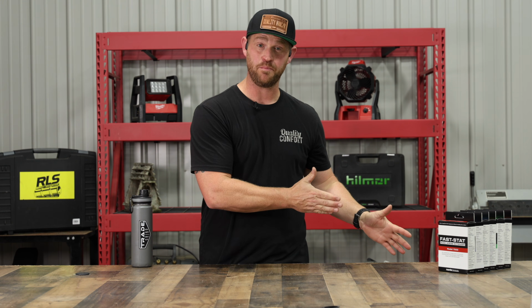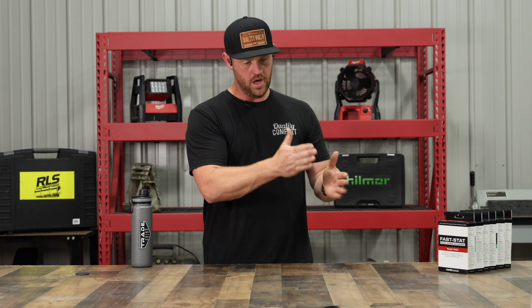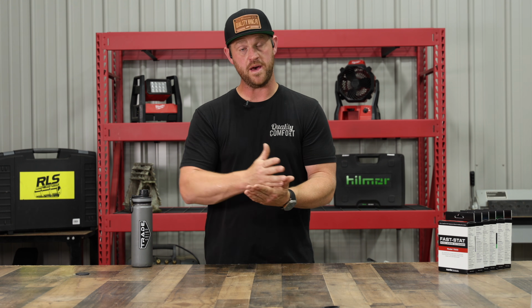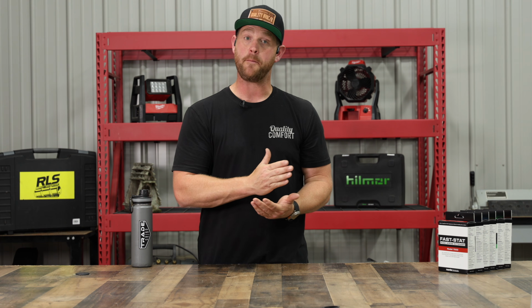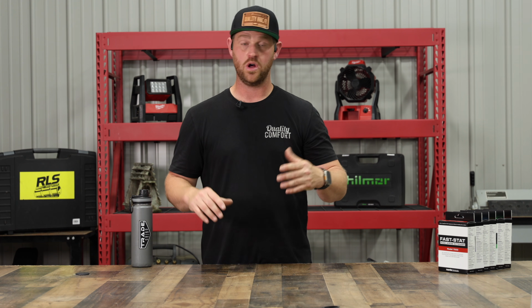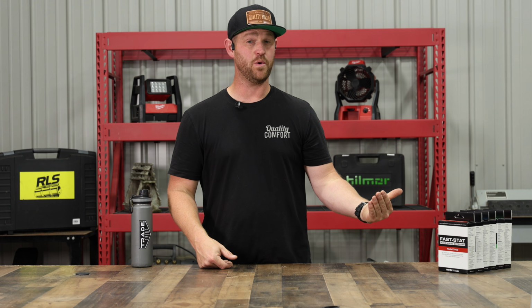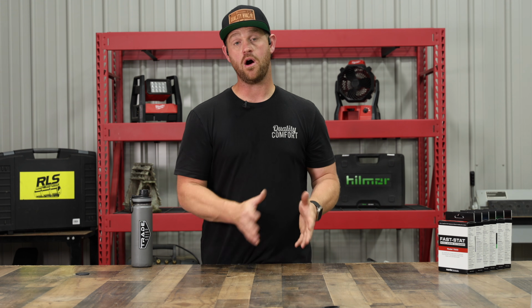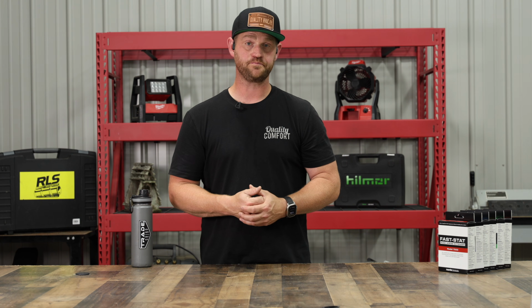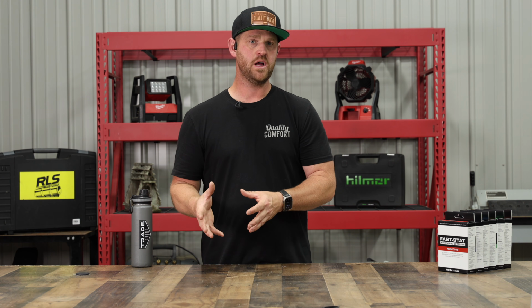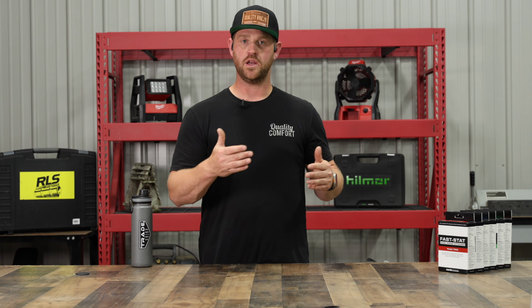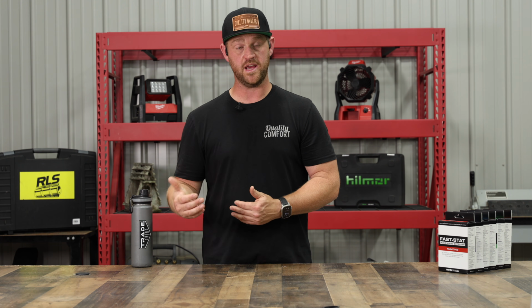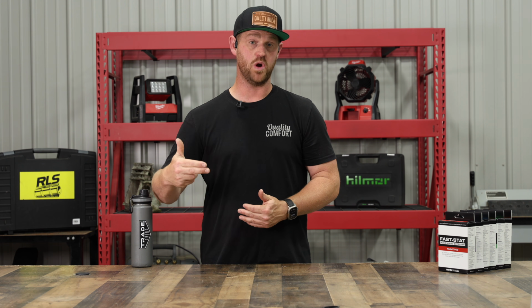Anyway, I digress. Getting back to the actual equipment itself. The two-stage equipment, the variable speed equipment, they are better at removing humidity. They're not ideal as if you, like I just talked about with a dedicated dehumidifier, but they are better. So that's one thing to note. And the reason they're better is because they're getting more runtime out of the system. In order for an air conditioner to remove humidity, it needs runtime. It needs to run and to squeeze the moisture out of that air.